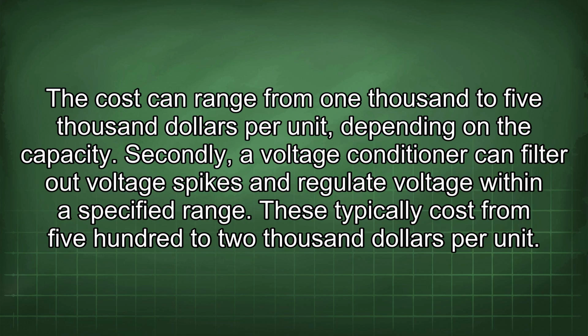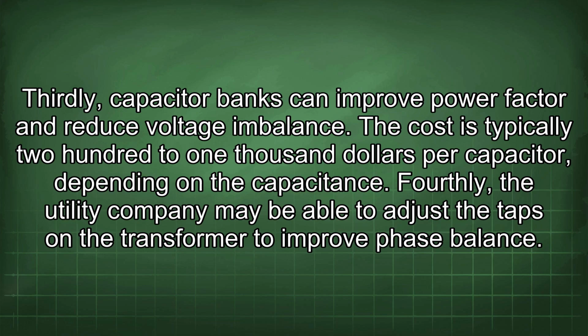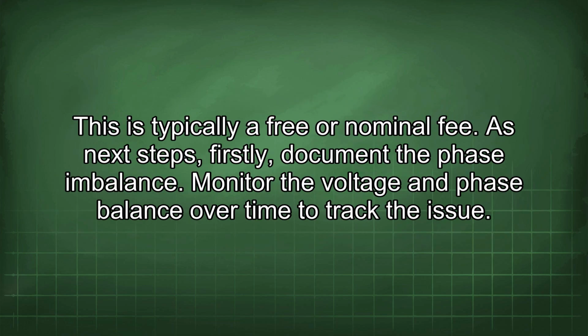Secondly, a voltage conditioner can filter out voltage spikes and regulate voltage within a specified range. These typically cost from $500 to $2,000 per unit. Thirdly, capacitor banks can improve power factor and reduce voltage imbalance. The cost is typically $200 to $1,000 per capacitor, depending on the capacitance. Fourthly, the utility company may be able to adjust the taps on the transformer to improve phase balance. This is typically a free or nominal fee.